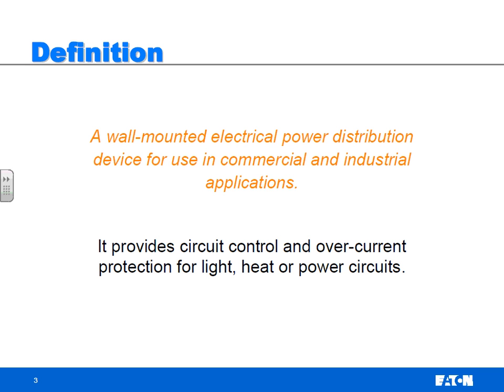So the definition of a panel board is a wall-mounted electrical power distribution device for use in commercial and industrial applications. Wall-mounted is the key on this one. It provides the circuit control, which is I can turn a breaker on and off to isolate my circuit, and overcurrent protection, which is for faults and overloads, for light, heat, power circuits, anything that you plug into.